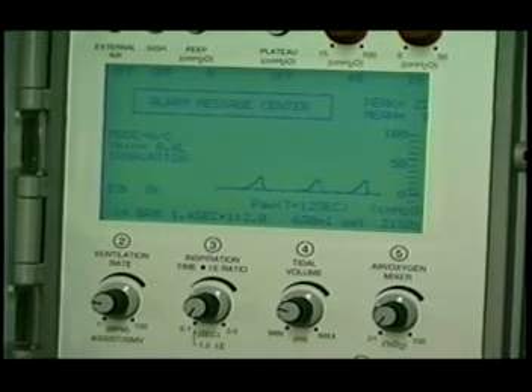The peak and mean airway pressure indicator continuously displays the peak and mean airway pressure of the previous breath. The digital bar graph indicator provides a continuous display of airway pressure. Its display range is from -10 to +100 centimeters of water, and its vertical resolution is 2 centimeters of water per bar. The airway pressure indicator is a graphic display of the most recent 12 seconds of airway pressure information. Its vertical axis is calibrated with the adjacent digital bar graph. Its horizontal axis is calibrated in 1-second intervals.